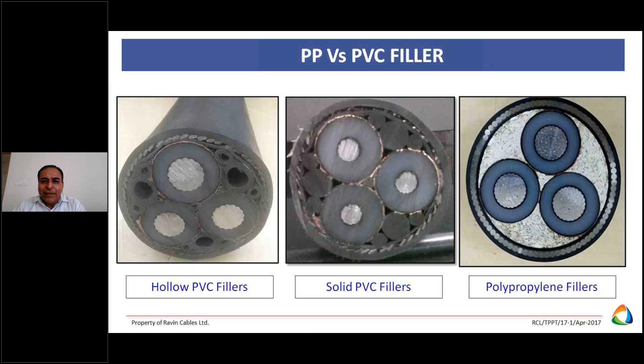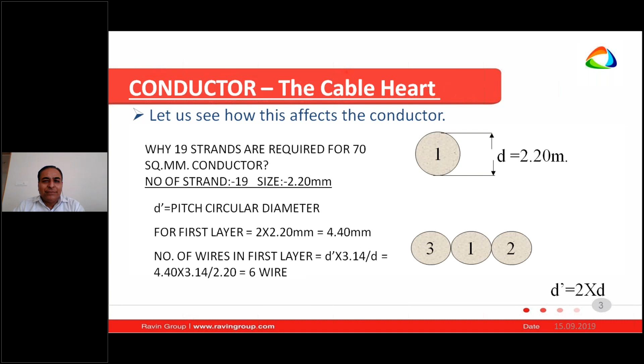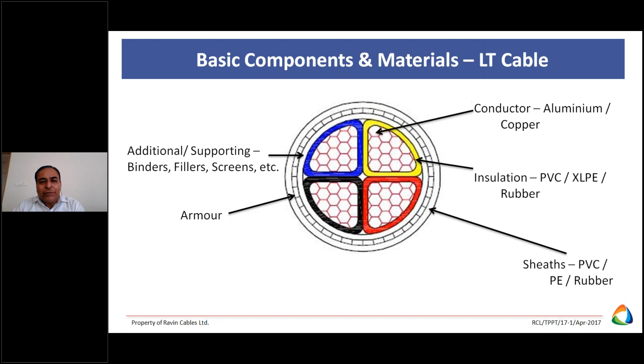Any question? Sir, I was muted. Actually, the question is, our cable size is suitable for the given loading, but it is getting rejected on short circuit rating, sir. Which type of short circuit, armor or conductor? The cable manufacturer is reluctant to give two short circuit ratings. He is just specifying the short circuit rating as 25 kA, not disclosing whether it is for conductor or armor. Basically, once you are saying 25 kiloampere, that means for the armor. But the fault level for the conductor is 40 kA per 1 second, based on transformer rating.